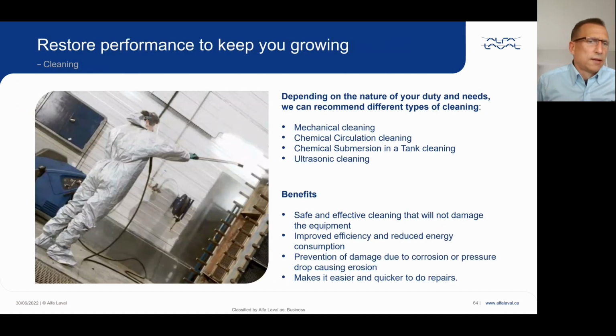In the life cycle of a heat exchanger, cleaning is probably the number one thing that gets done to it. I don't know any exchanger that doesn't need a clean job once in a while. When you have a piece of equipment with a hot and cold fluid going through it, it's a good target for fouling. Velocities usually slow down as fluid goes through an exchanger, so that's when debris builds up.